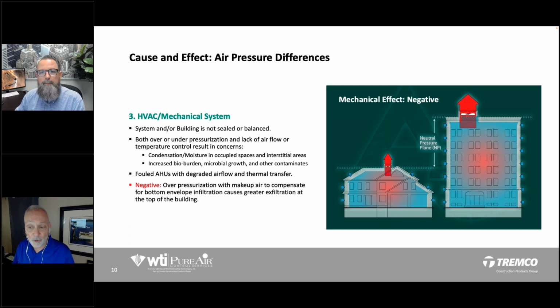Not only are you pulling in outside unconditioned air, but you're pulling in other pollutants as well. As you can see, the neutral pressure plane is up to the top of the building, so you're pulling in air from all sides. This happens in taller buildings, or even in your home. If you're running three bathroom fans like crazy, you could create that negative pressure very easily.